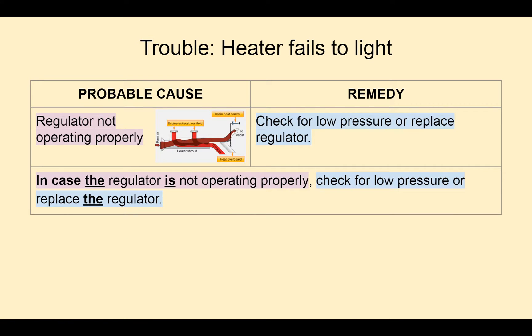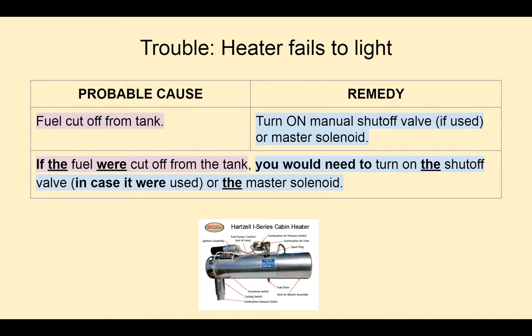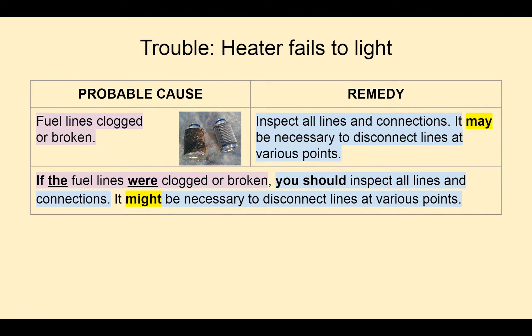Here we have another example. In case the regulator is not operating properly, check for low pressure or replace the regulator. Or, if the fuel were cut off from the tank, you would need to turn on the shut-off valve, in case it were used, or the master solenoid. Finally, if the fuel lines were clogged or broken, you should inspect all lines and connections. It might be necessary to disconnect lines at various points. Note 'may' and 'might' in yellow, since this will be explained later.